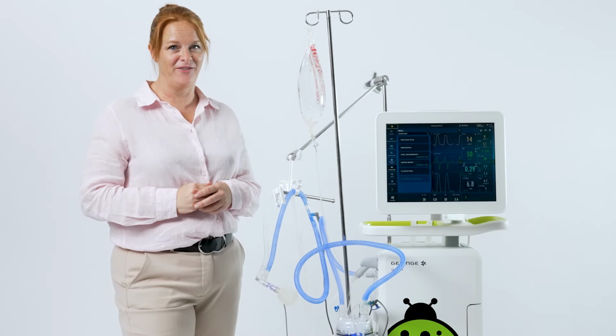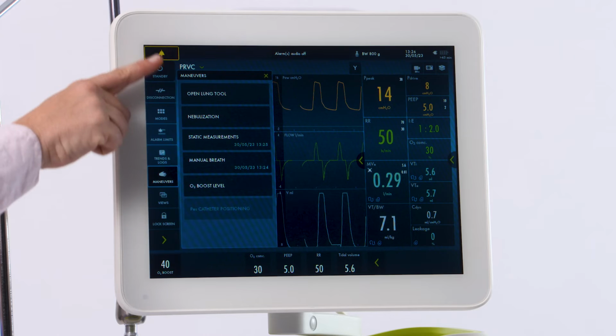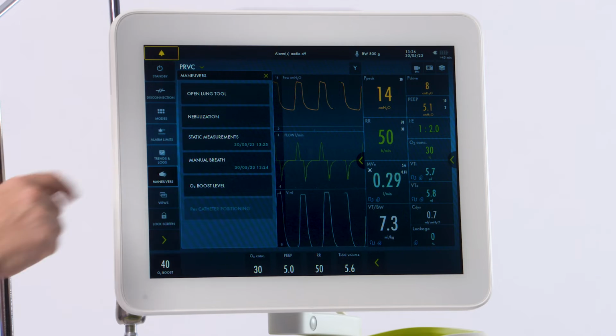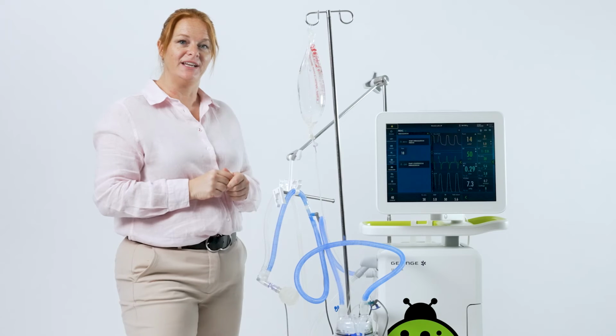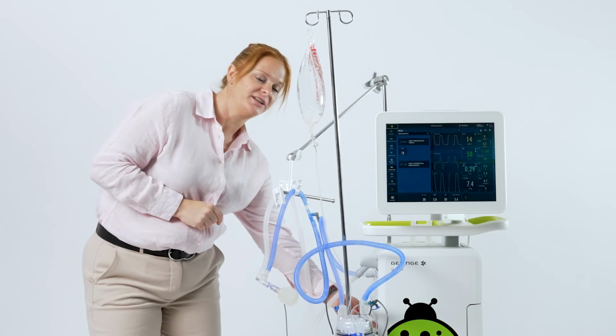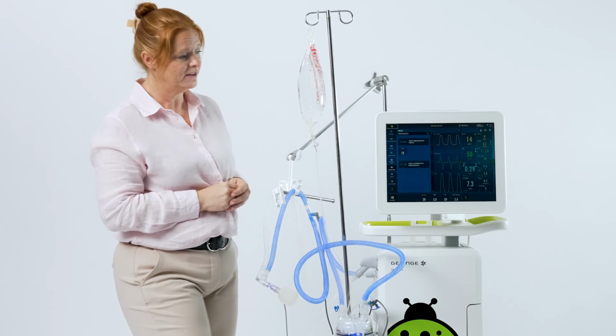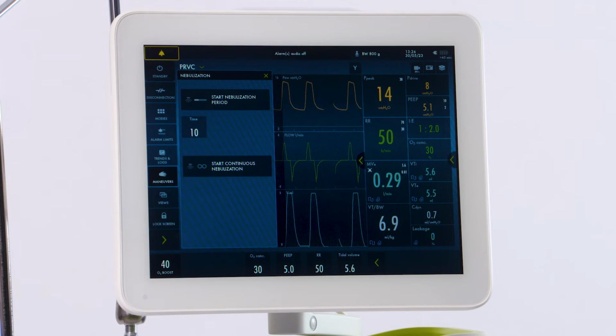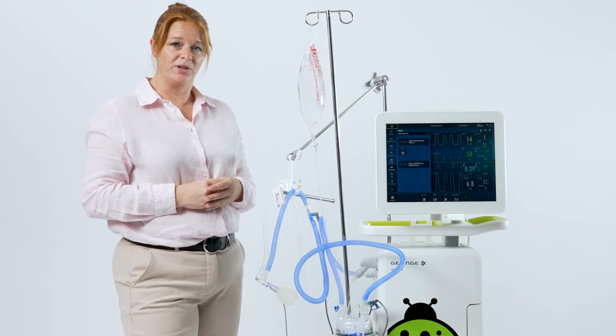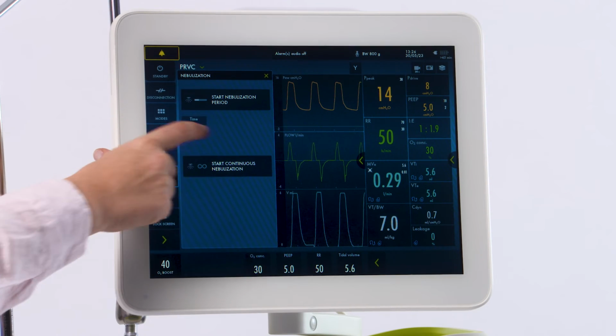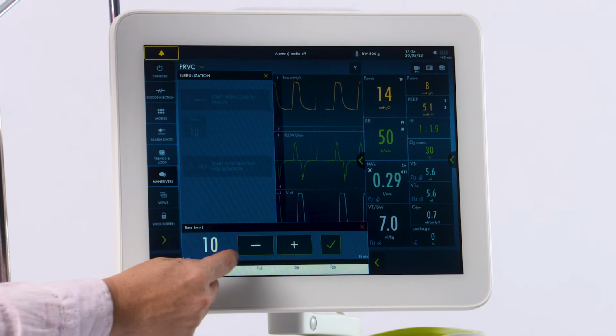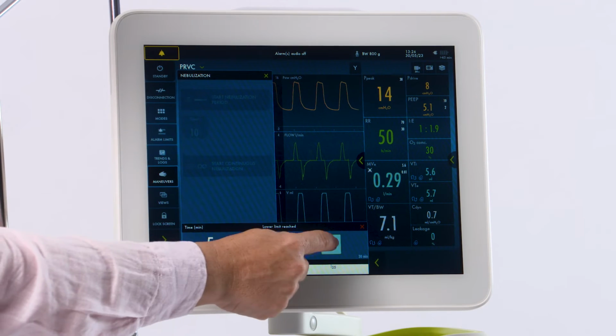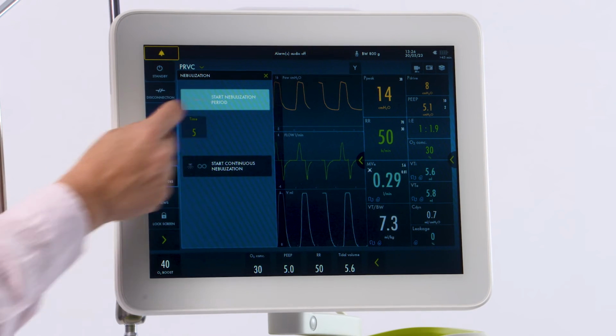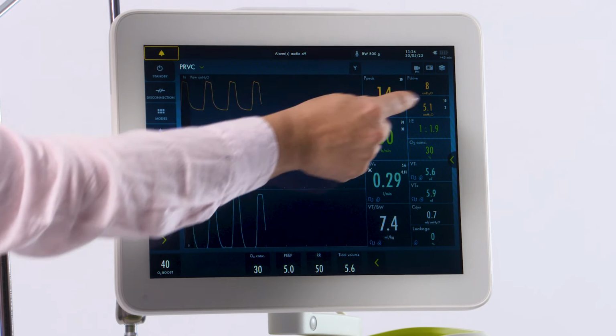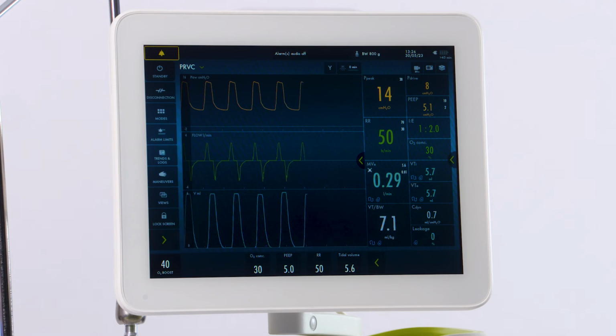Aerogen is built into every single ventilator and is accessed underneath your nebulization tab. Once you select it, you will then plug in your Aerogen located on the side of the vent. You will see that there is an intermittent or continuous. There you can choose which one you would like. You can do anywhere from 5 to 30 minutes. Hitting accept, you will then see your nebulization started at the top.